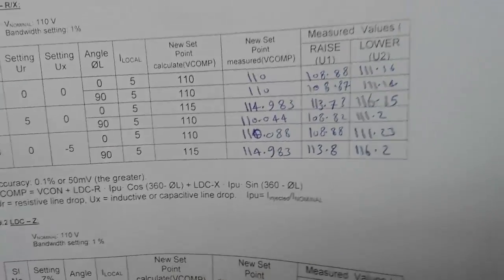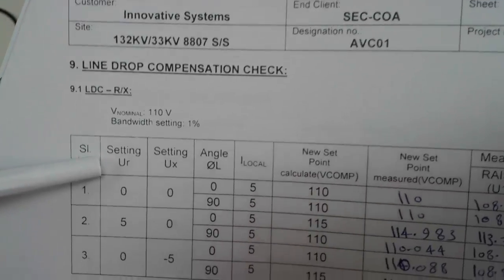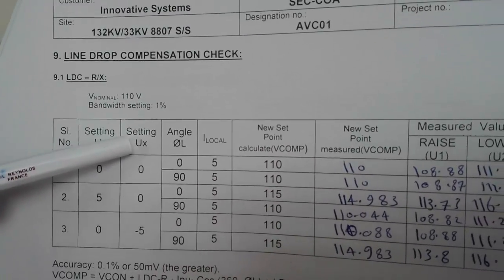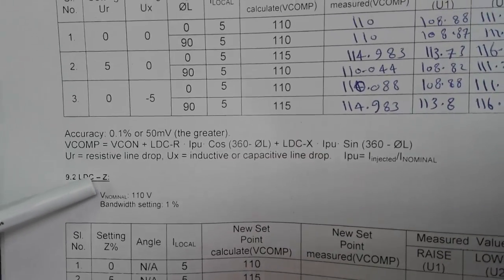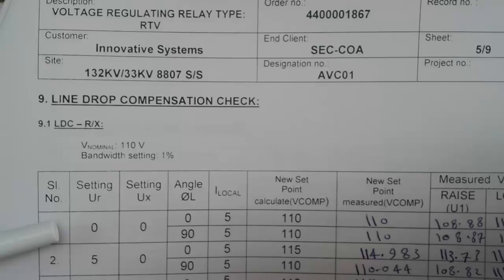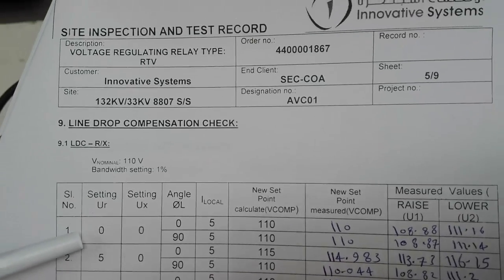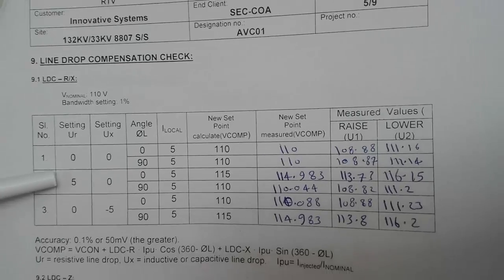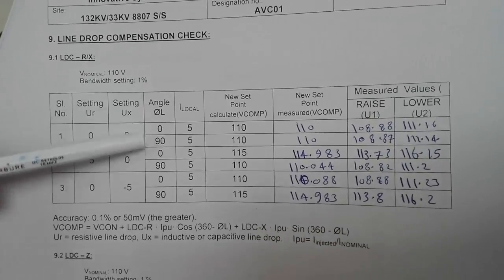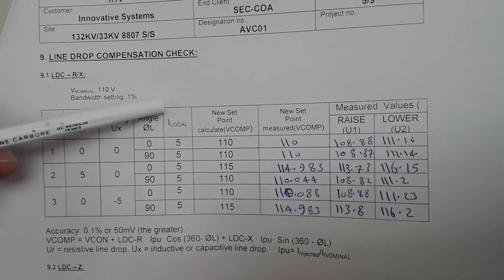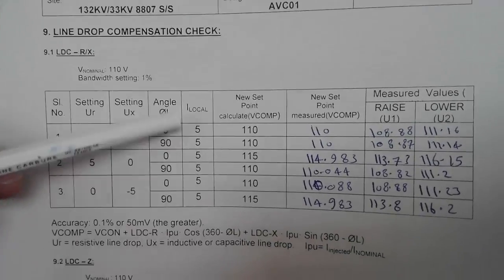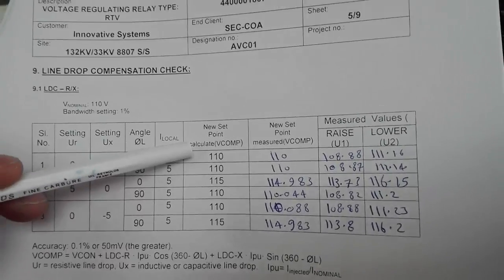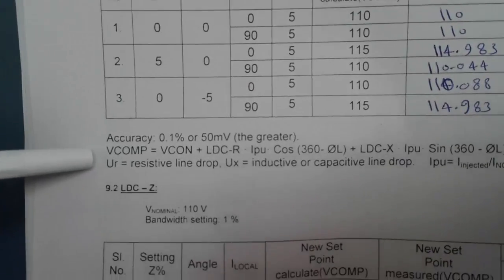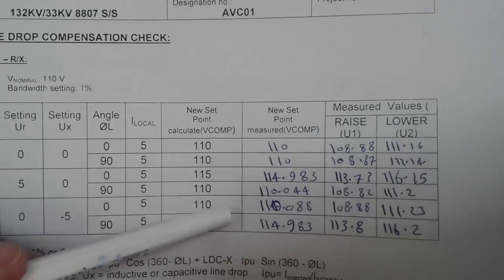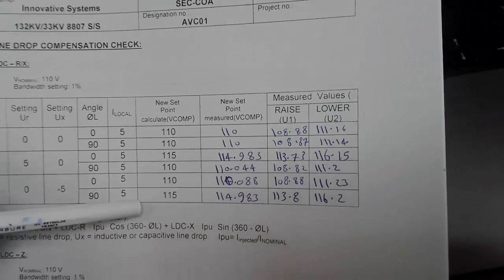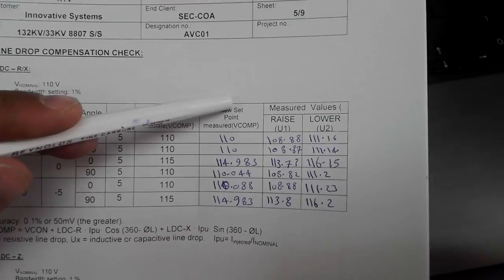Simply we have to follow this formula, using the R parameter and X parameter, and then we will do it for the Z parameter. First we will perform it for R and X parameters. The R and X parameters we will use are already provided by this table, and then we will change the angle accordingly, and keep the current constant at 5 amps. These are the expected values derived from this formula. Now against these expected values we will find the new set values.